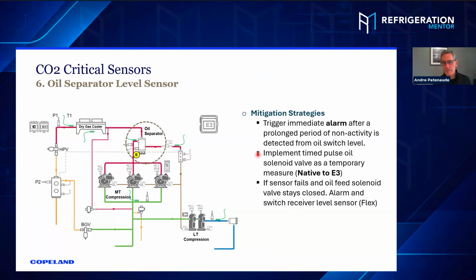So, if after X amount of time, you'd have to build that in, you would implement a time pulsed solenoid valve in order to feed the reservoir. And you've got other sensors on the reservoir, but that is something that's native to the E3 that you can do. If the sensor fails and the oil feed solenoid stays closed, you'd have to alarm and switch to the receiver level, flex release receiver level. Let that solenoid be controlled by the reservoir level.